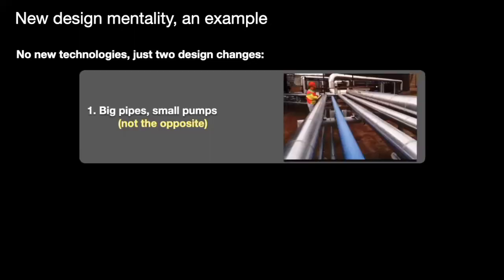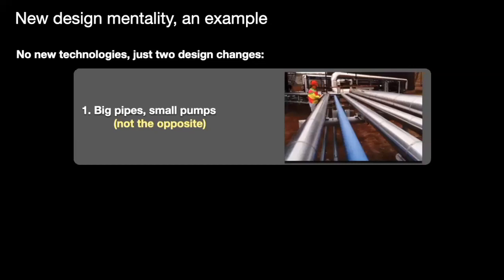Such radical savings require two changes in design mentality, design process. First, we specify big pipes and small pumps, not small pipes and big pumps. Friction in a pipe falls as nearly the fifth power of diameter. So how fat should the pipe be to optimize the friction?